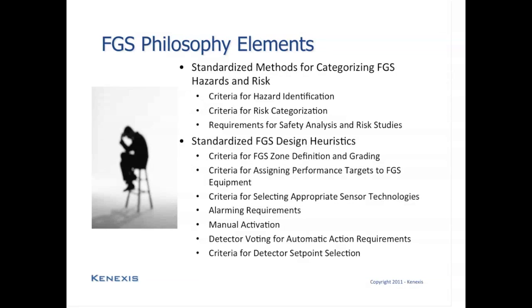So those are the types of criteria that will determine whether or not an equipment item or an area is even considered for fire and gas system mitigation. If areas are going to be considered for fire and gas system mitigation, then criteria is going to be required to categorize the degree of risk that equipment presents. So some equipment, such as high pressure compressors, are going to pose a much higher risk and thus require much more mitigation than lower risk systems such as methanol storage tanks for methanol injection.